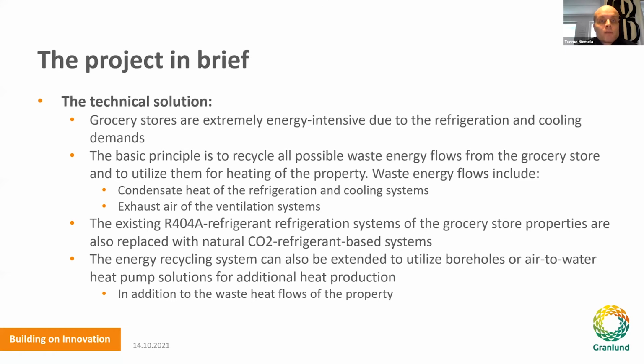The basic principle, which I'll demonstrate a bit better, is to recycle all possible waste heat flows back to the grocery store and utilize them for heating the property. The main heat flows are condensate heat from the refrigeration and cooling systems. In some cases, larger grocery stores or hypermarkets also have exhaust air from ventilation systems, including air handling units without proper heat recovery, so we can collect that heat using this heat pump system.